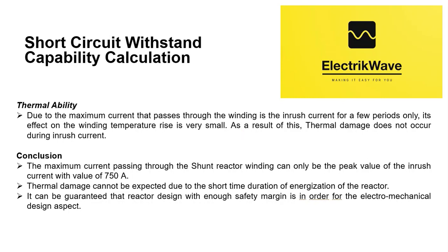Thermal ability: due to the maximum current that passes through the winding being the inrush current for only a few periods, its effect on the winding temperature rise is very small. As a result, thermal damage does not occur during inrush current. Conclusion: the maximum current passing through the shunt reactor winding can only be the peak value of the inrush current with a value of 750 ampere. Thermal damage cannot be expected due to the short time duration of energization of the reactor. It can be guaranteed that the reactor design with enough safety margin is in order for the electromechanical design aspect.